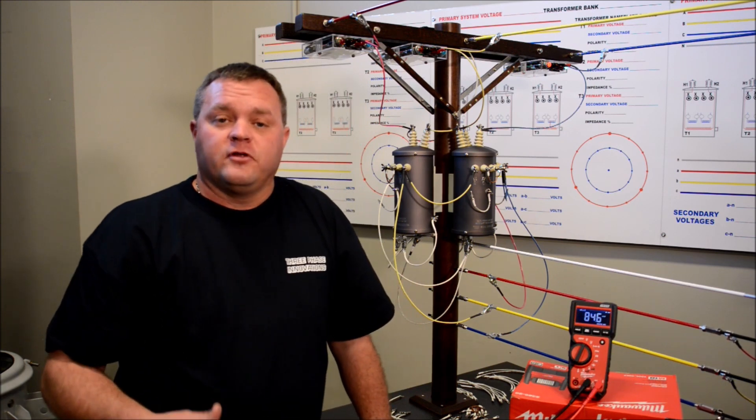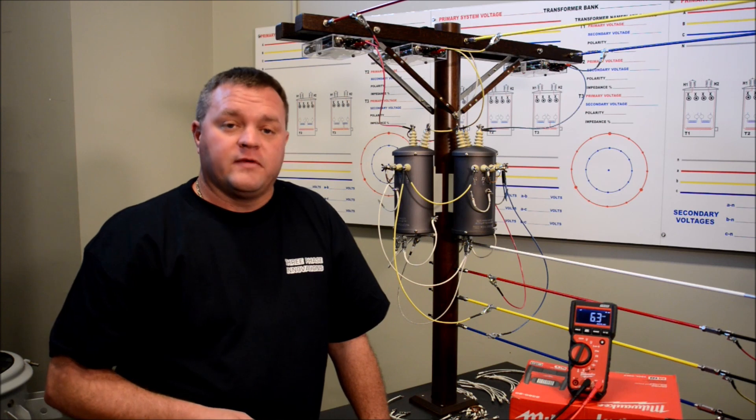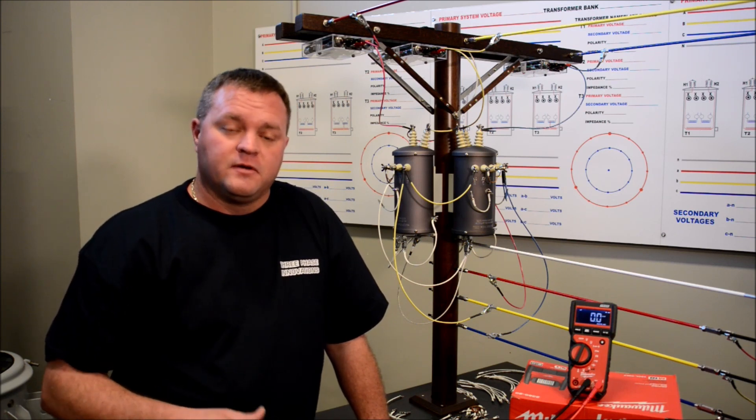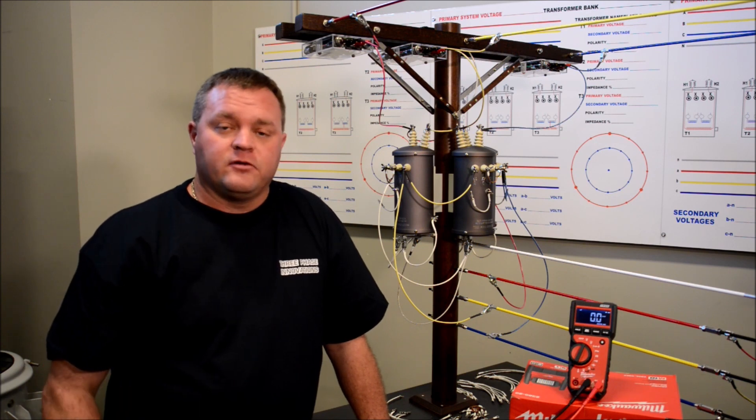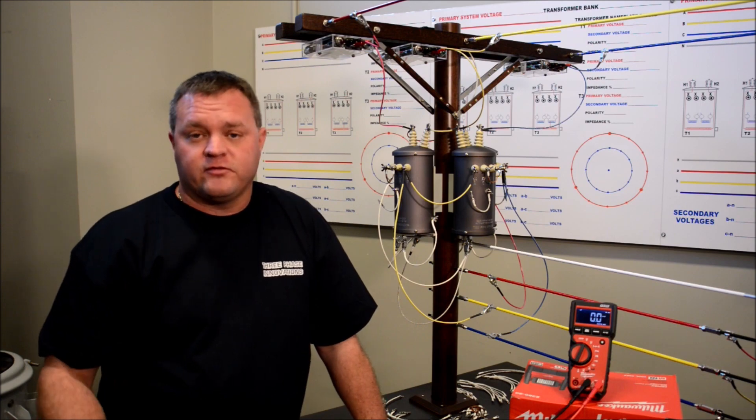Again, this is just to let you be aware of that 208 high leg. You always need to be aware of that whenever you're reconnecting to this bank. Mark it, put it over the side, and mix it back into the rotation correctly. Thanks again for watching Three-Phase Innovations. Check us out.